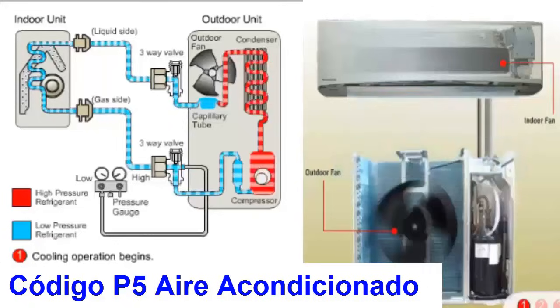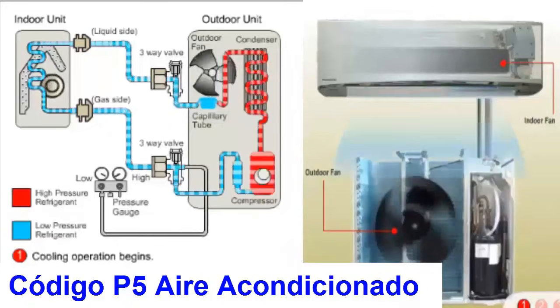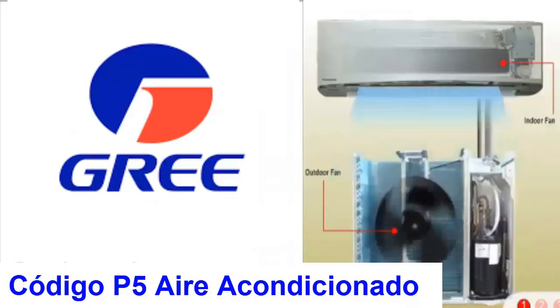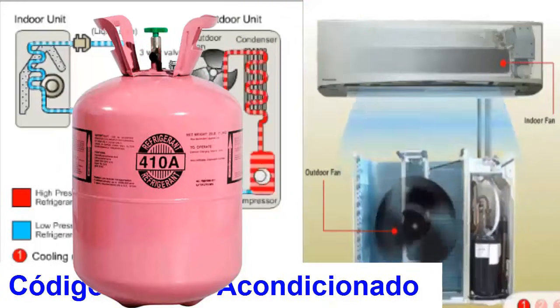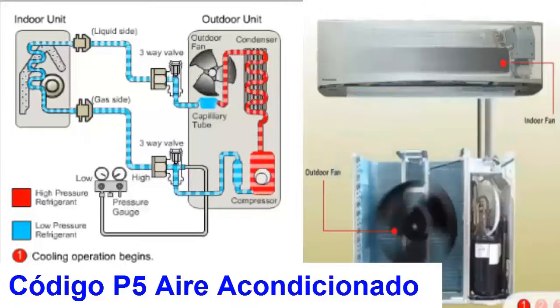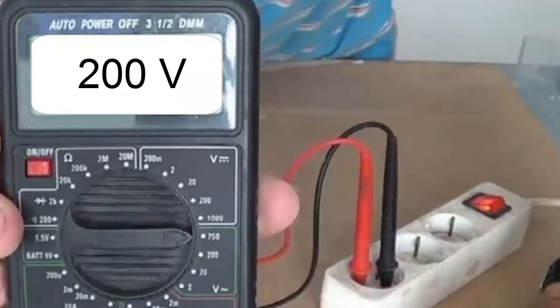4. In the case of GREE, the P5 code signals compressor current protection. It is recommended to disconnect the electricity from the equipment for several minutes and check if the problem persists. It is recommended to verify that the system contains the appropriate amount of refrigerant and heat exchange to ensure proper compressor operation, avoiding overpressure for the compressor. It is also important to measure the supply voltage from the outside, and rule out false contacts or cable problems.